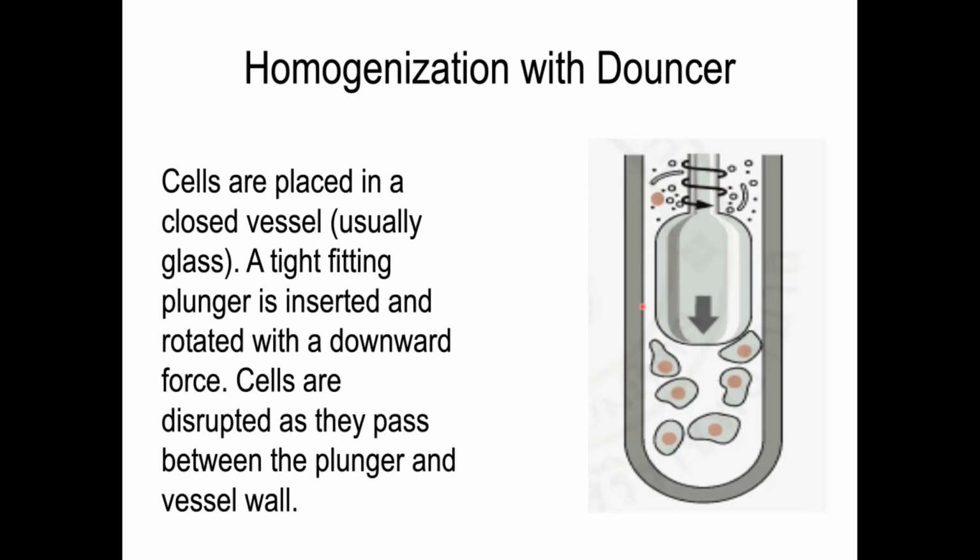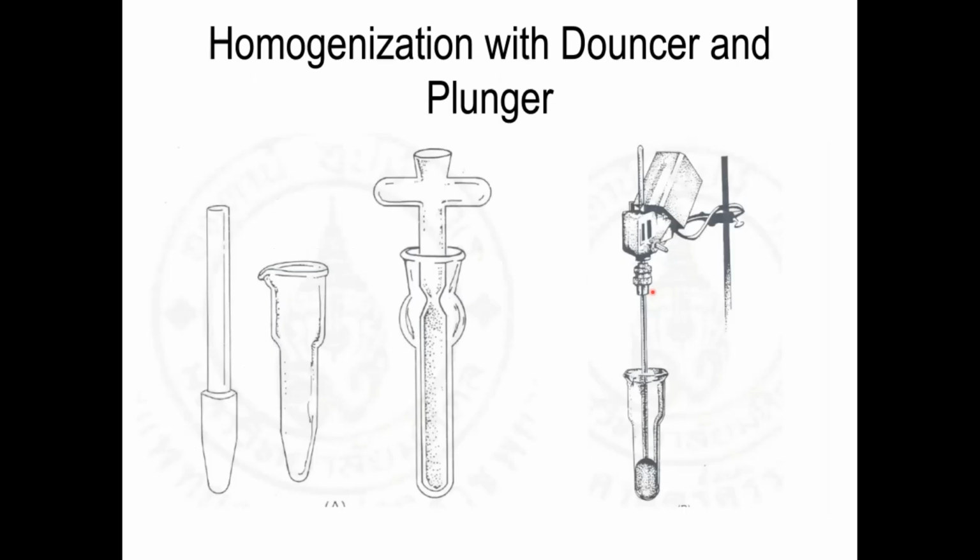and the vessel wall. And these systems are manufactured by special companies that are specialized in scientific glassware that is used in laboratories. They are usually not very expensive, and you can buy plunger and vessel systems with exactly defined distances to the wall in the micrometer range. That means you can adjust the space width here, which helps you to deal with larger cells or with smaller cells that you can then very easily disrupt with this technology.